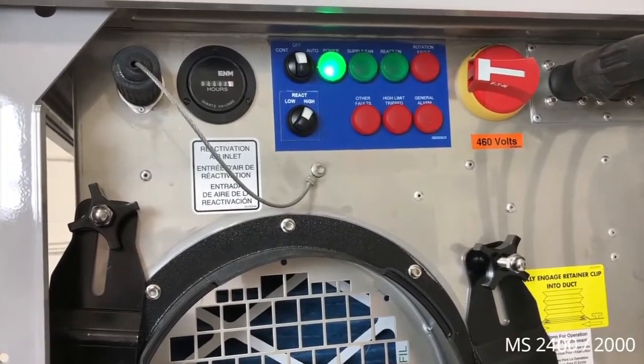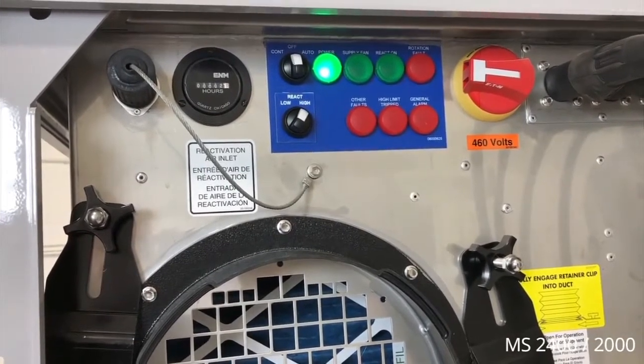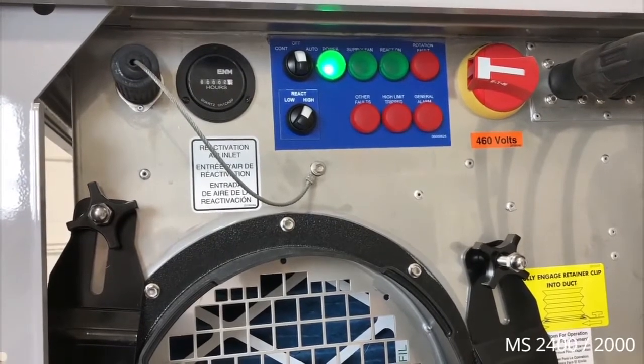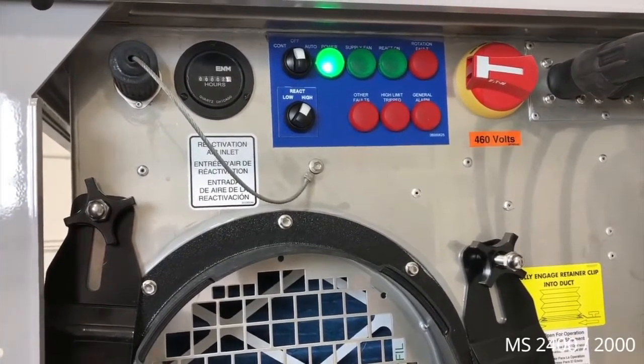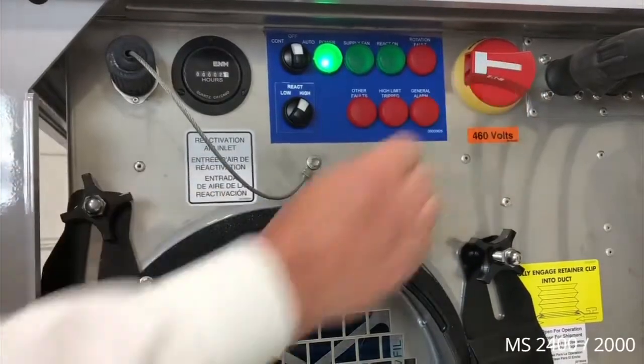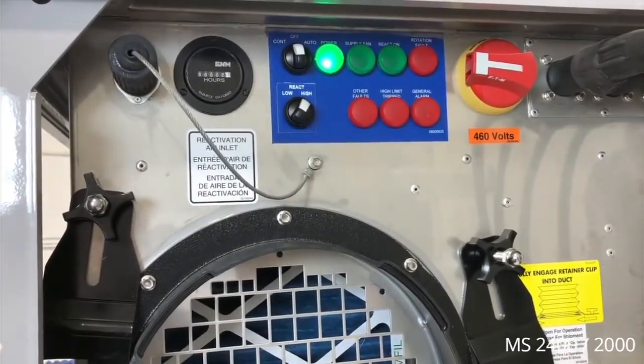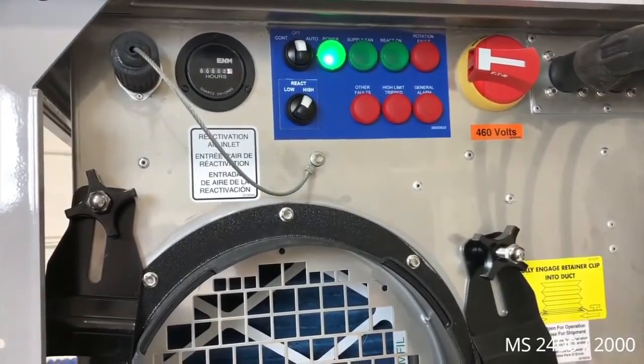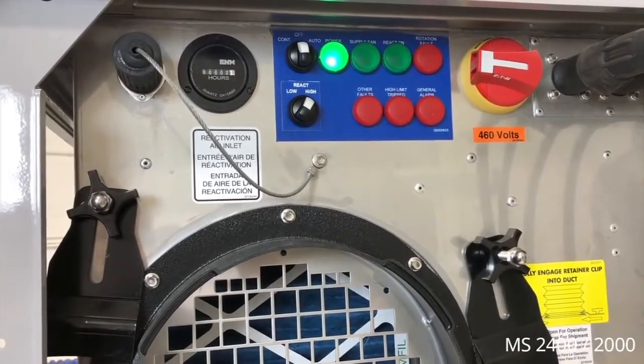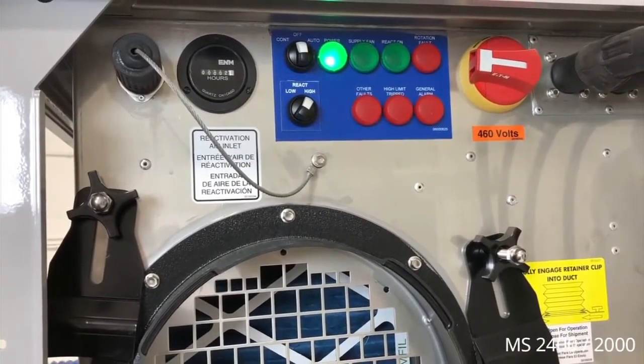The life of the electric heaters is directly related to how the unit is turned off. The heaters operate at temperatures of 400 to 500 degrees during normal airflow operations. If you simply turn the disconnect switch off, the electric heaters can exceed their specified temperature and actually rupture and create a problem with the current.